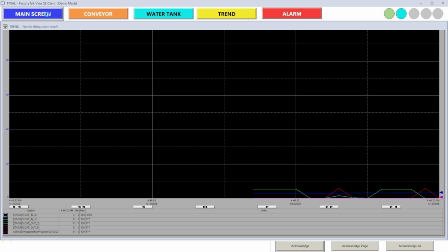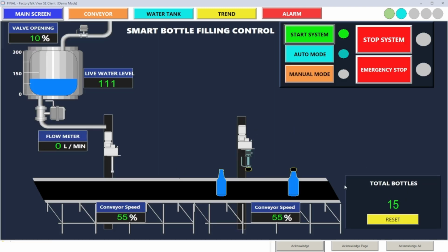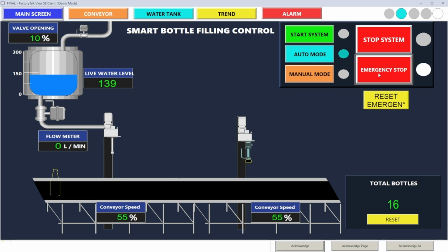Moving to the trend screen, this shows the water level in the tank over time. It's a useful diagnostic tool to monitor system behavior. The tank level is controlled by analog values, and I've configured alarms for both high and low levels. On the HMI, if the level drops too low, you get a blinking warning and a sound, depending on configuration.